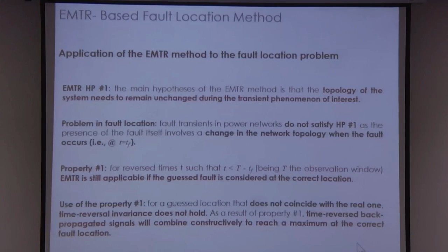In reverse time, when we don't know the fault location, what we do is define a number of guessed locations. If our guessed location matches the true fault point, then both the medium and the network will have the same topology, and only in that case will the theory hold and we'll see energy concentration. We use this property to develop our method.